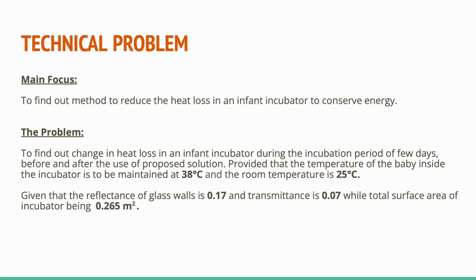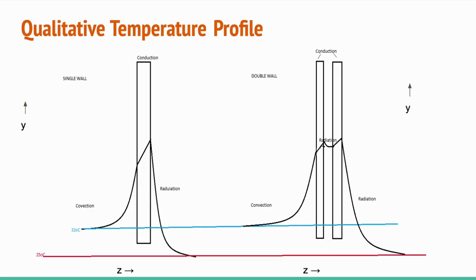Our problem statement was to find the change in heat loss in an infant incubator during the incubation period, before and after the use of the proposed solution — double wall incubators — provided that the temperature inside the incubator is to be maintained at 38°C and the room temperature is 25°C. Given that the reflectance of glass walls is 0.17 and transmittance is 0.07, with the total surface area of the incubator being 0.265 m². Using the same coordinate system, we can observe the temperature variation in 2D, with two temperature profiles for the two cases: single wall and double wall. We can see the modes of heat transfer like convection at the surface of air, conduction in the wall, and radiation in the temperature profile.